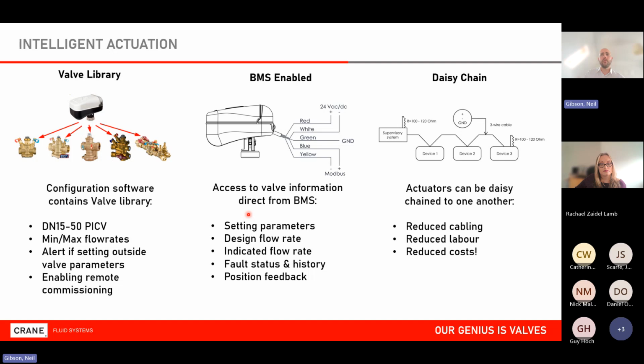As well as that, all of those dip switch settings that I mentioned before, the direct to reverse, the equal to linear percentage, all of those are now done via a register. There's different registers for all of these. We can find the dip switch settings effectively built within there. We can also get separate registers to give us flow rate based on positional feedback. So all of this information is now at our fingertips.